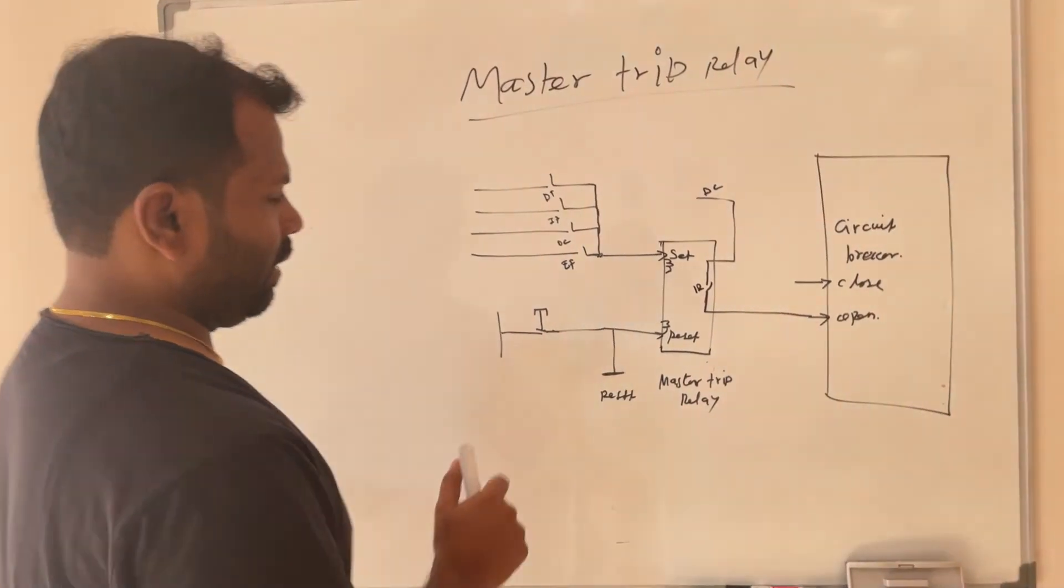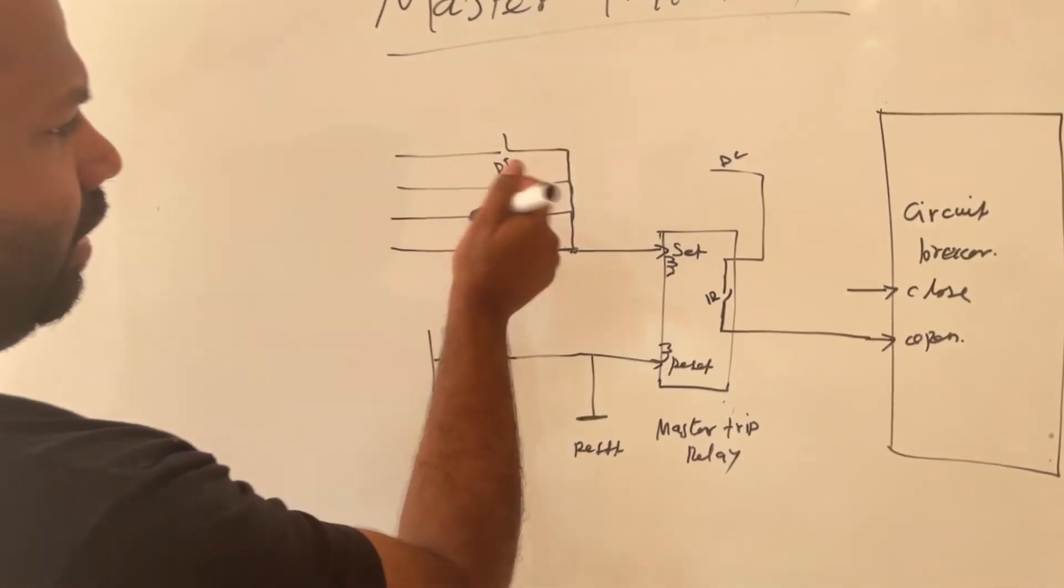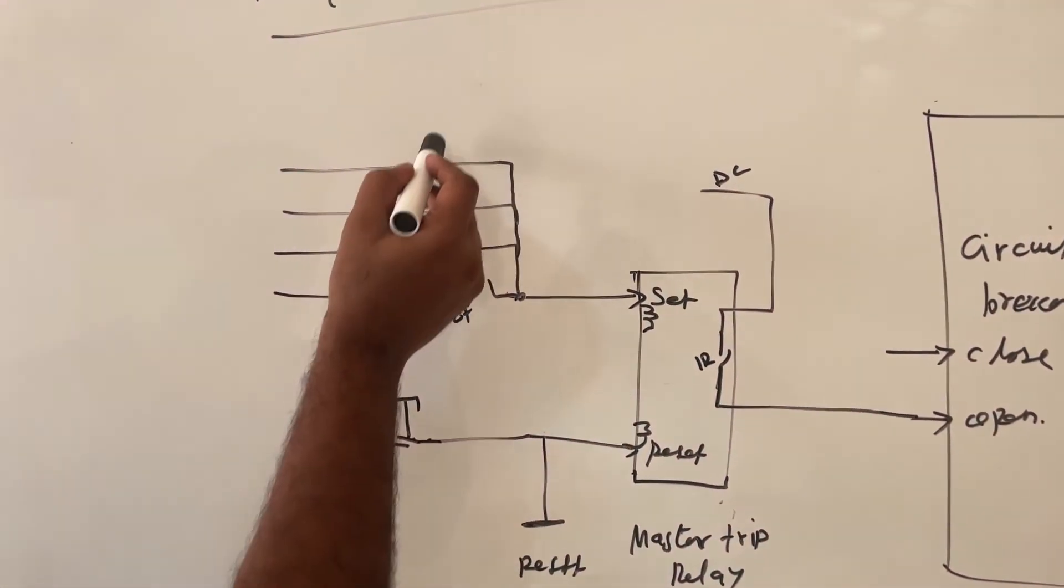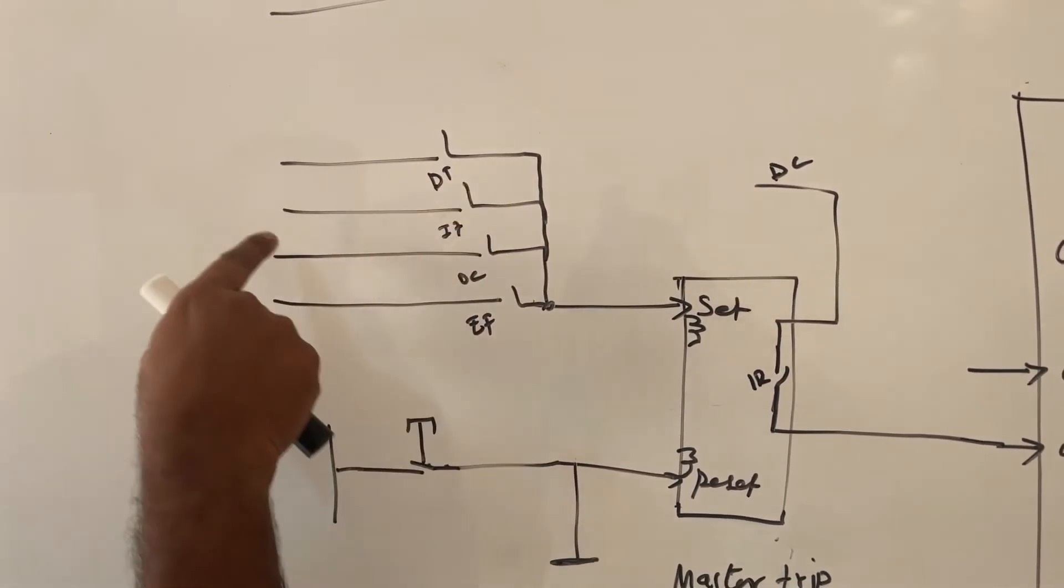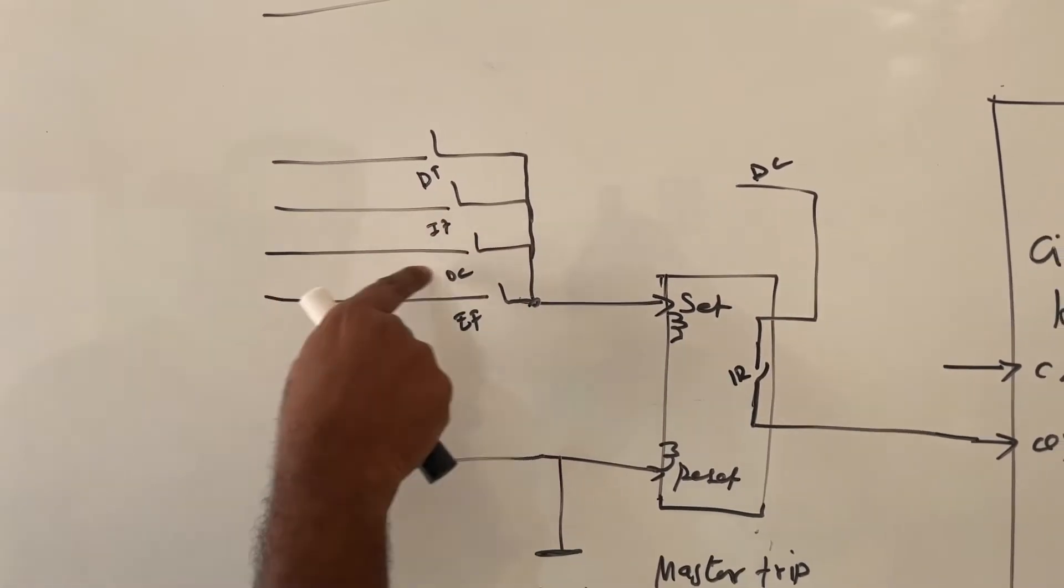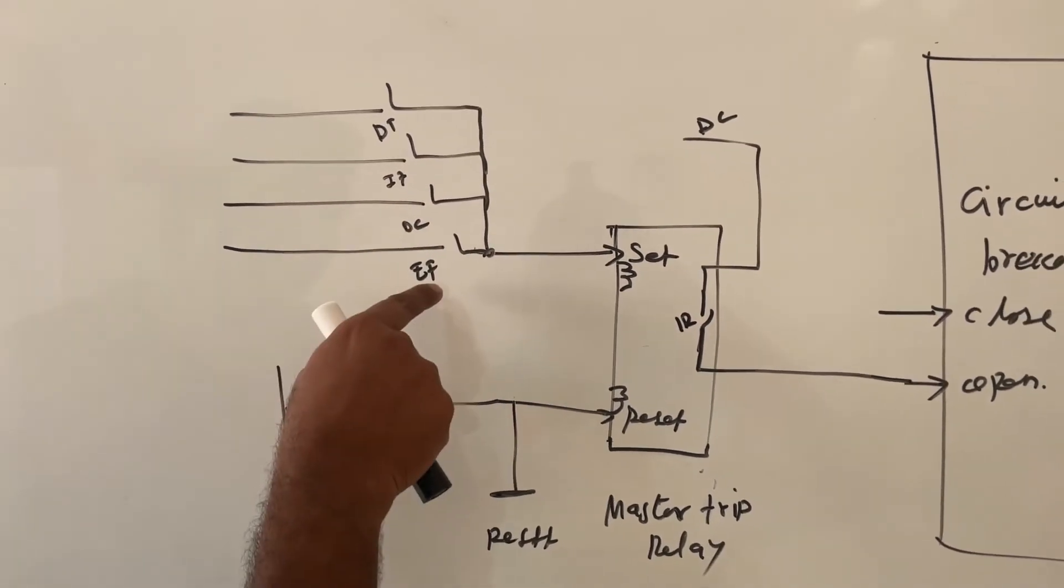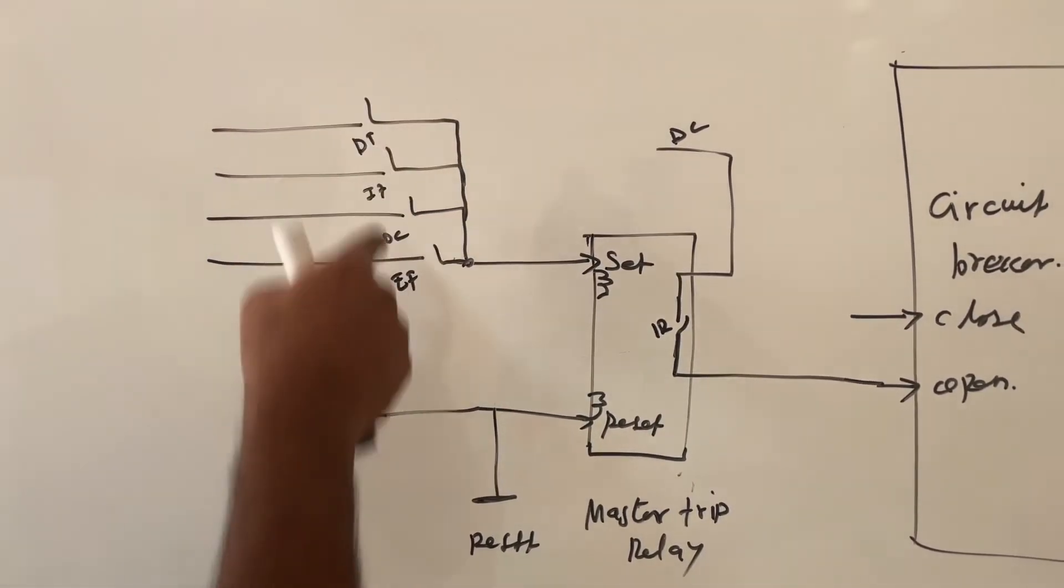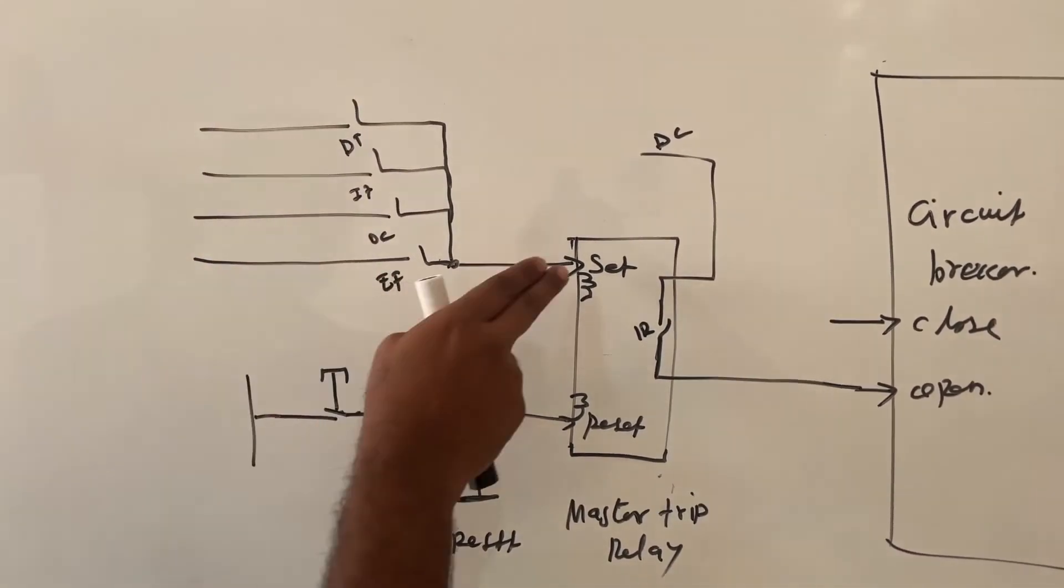To this set coil or trip coil, external relay contacts will be connected parallelly. This signal coming from differential protection relay, this signal is coming from instantaneous trip relay, this trip signal is coming from over current relay, this signal is coming from earth fault relay. Like this you can add any trip command parallelly to this master trip relay set coil.